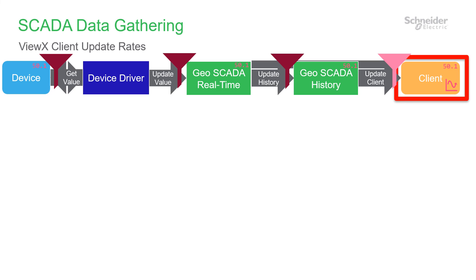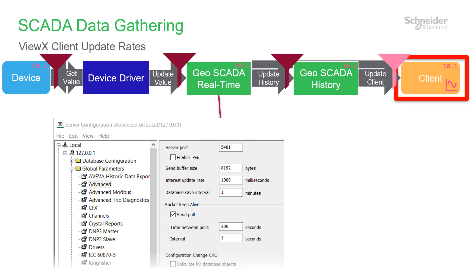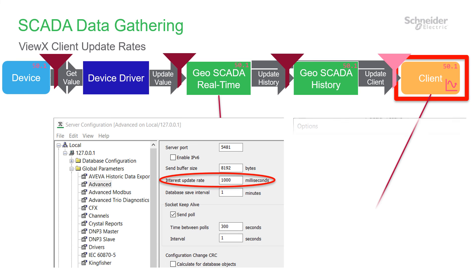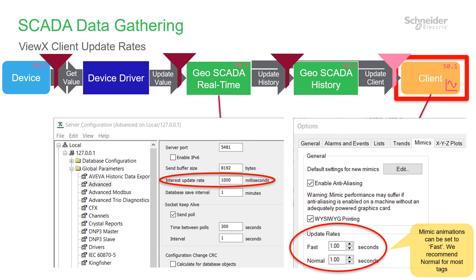Finally, you have a line of defense in updating client displays. While it might not seem a problem to update client displays rapidly, you need to consider how this scales up when the number of clients increases. At the server, we recommend a minimum on-change or interest update rate of one second — use the server configuration tool to change this. And at the ViewX client, we recommend that both fast and normal data update rates are one second too. These settings are in the ViewX options menu available to administrators. Users may not notice these minor changes when the screen is updated, although they will see improved performance when trends are displayed and updated or when they have multiple screens. So it's worth doing.